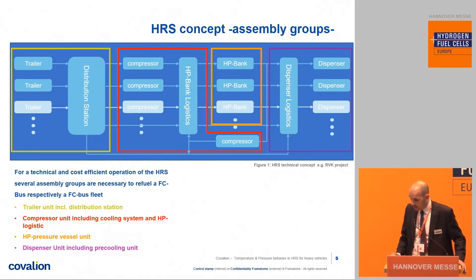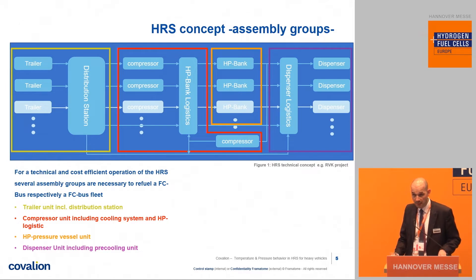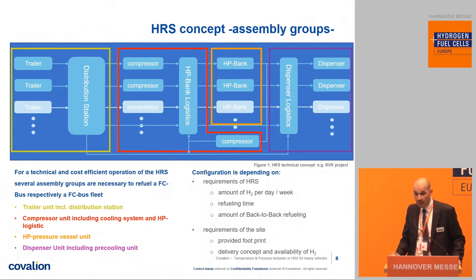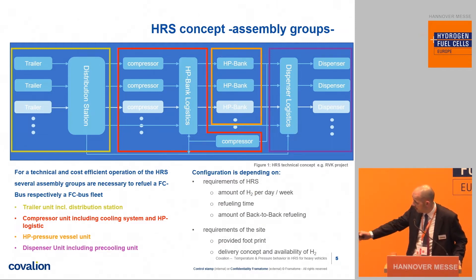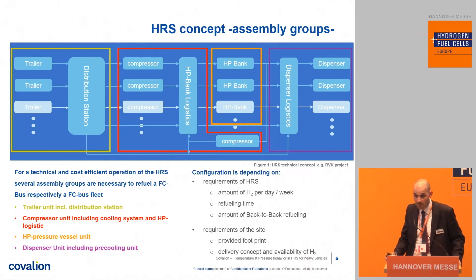The whole hydrogen refueling station consists of different assembly groups, and it's quite important that they all fit together to get a technically and cost-efficient way to operate the station. The configuration depends on the requirements: the amount of hydrogen per day or week, the refueling time, and the amount of back-to-back refuelings. Furthermore, there are site requirements like the provided footprint, the delivery concept, and the availability of hydrogen.